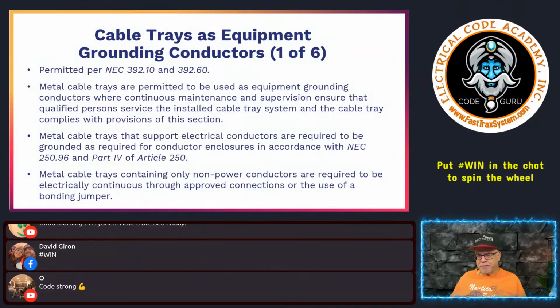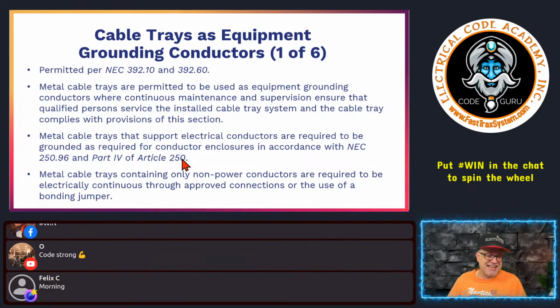Okay. So there you go. Now, metal cable trays that support electrical conductors are required to be grounded as required for conductor enclosures in accordance with 250.96 and Part 4 of Article 250. So if you've got a metal cable tray, as always, you're putting conductors in it, then what happens is, again, you're putting in conductors that could energize the metal parts. And of course, you have to meet all the other grounding and bonding requirements within the National Electrical Code, specifically Article 250. So that should be a no-brainer. If you're going to be dropping conductors in a metal tray, then at some point you don't want any isolated part of the metal tray, because if it did get energized, then you could have some isolated metal part that somebody could come in contact with.